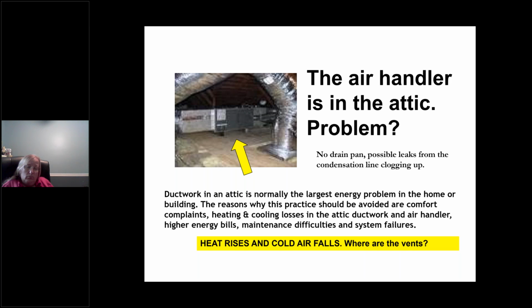With an air conditioning unit, if the condensation line gets clogged, the water has nowhere to go but onto the floor of the attic, which invariably drips into the drywall ceiling below. People will look up and think they have a roof leak, but not necessarily. It could be an air handler in the attic — you can tell because the vents are all in the ceiling or at the top of the walls. If that's the case, there should be a pan underneath to collect the water, and properly it should have an alarm installed so that if the pan fills up, it shuts the furnace down so it stops producing more condensation.